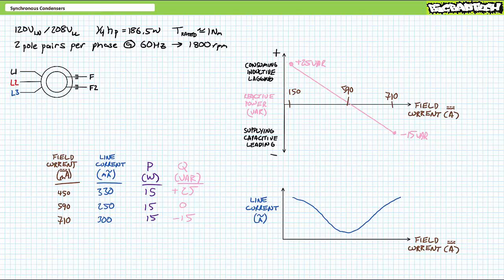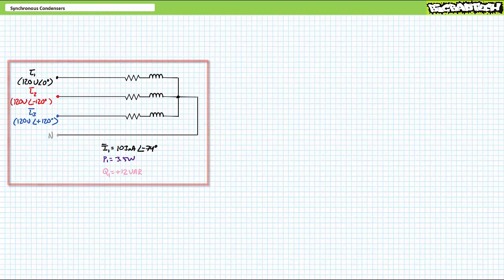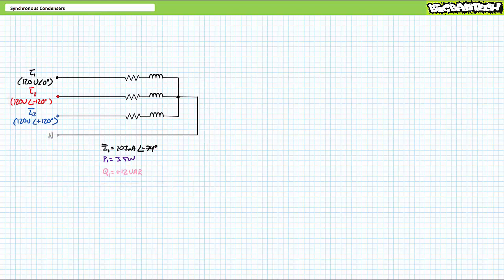Our first load scenario is a balanced Y configuration of a slightly inductive impedance. In the non-power factor corrected scenario, each phase appears to draw 100 mA of current where current lags each phase voltage by a relative 74 degrees. Each load appears to be consuming roughly 3.5 watts of real power and positive 12 VARs of reactive power. This is well inside the correction range of this particular device, and we would expect to slightly over-excite the rotor to supply an equivalent amount of negative reactive power.